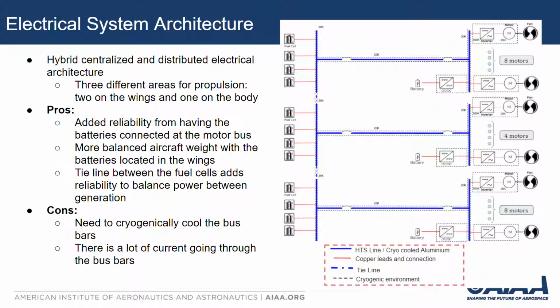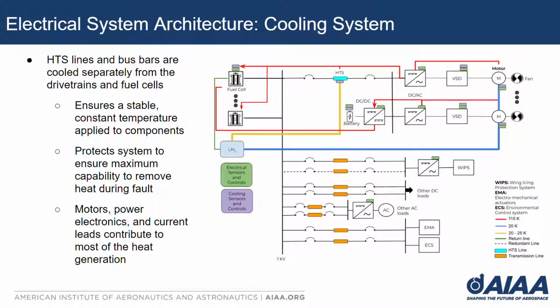However, in this configuration, because we're using one HTS line to send power from the fuel cells to the bus bars, we need to cryogenically cool both the bus bars and the HTS lines so that we can limit the losses in those components. Here we have our cooling system.